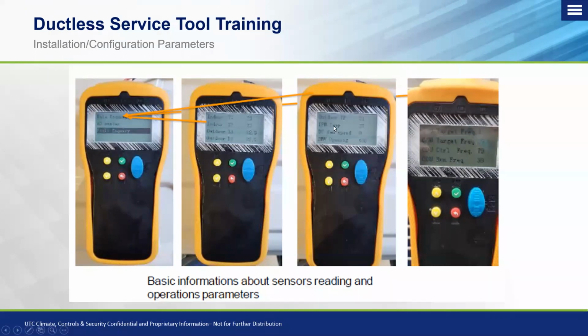Okay, you'll also see on here different temperature ratings for your drive board to make sure that it's not overheating. Your DC fan speed, which we looked at in RPM, which is where we can verify that. You'll see your PMV opening on there, 480 pulses. And you'll see different target frequencies, control frequencies, and run frequencies. And we talked about that at the beginning of this class when we were understanding target versus run. This is where you can confirm the information of the current running frequency, which you should see on the main board, and then more importantly, the control frequency of where the unit's trying to maintain at, or that target.